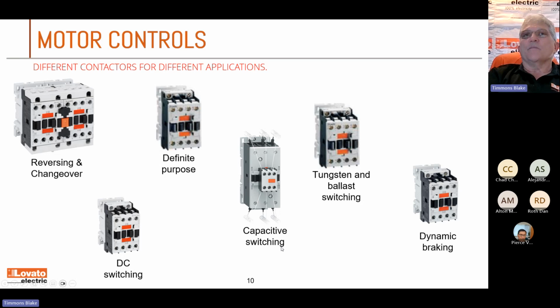We have some other ones that are for capacitive switching. And that little adder block on the front of it is a resistor contact, a set of auxiliary contacts with a resistor in it. So when you go to pull that in, it's got an early make contact on it. When you pull in a capacitor bank, you're going to bleed off some of that surge. We've all seen that arc when a capacitor shorts. You want to bleed that off a little bit, and then you can close your contactor. Makes them last longer. That's a little kit on ours that you can put in the front of it.